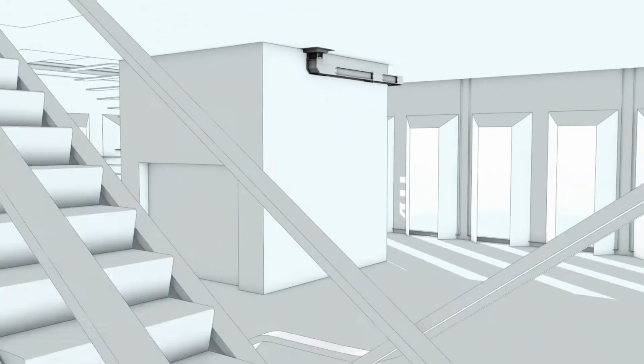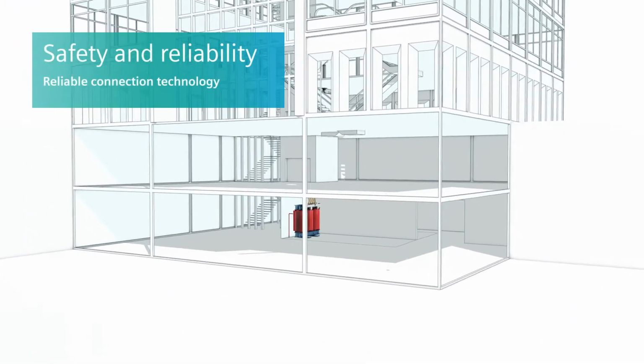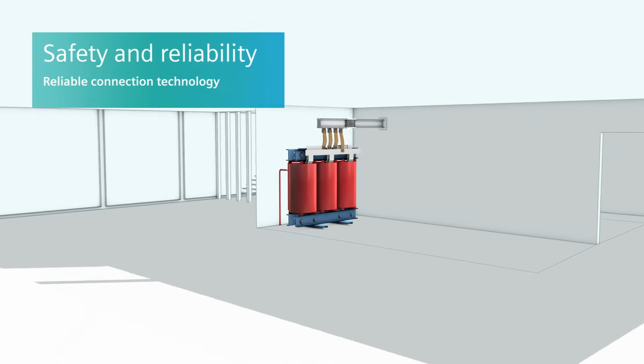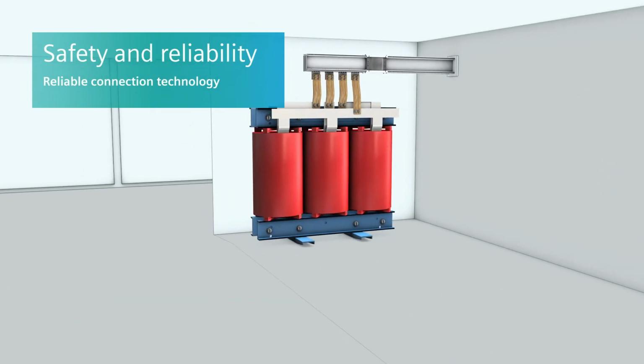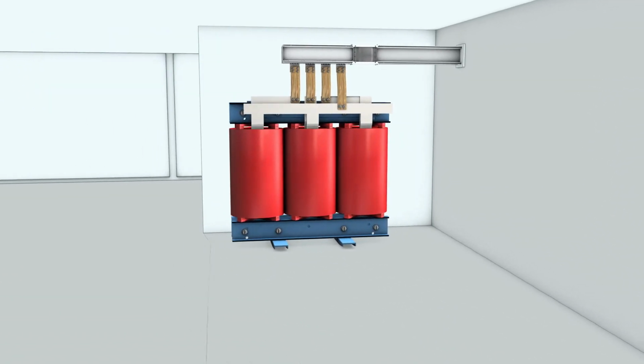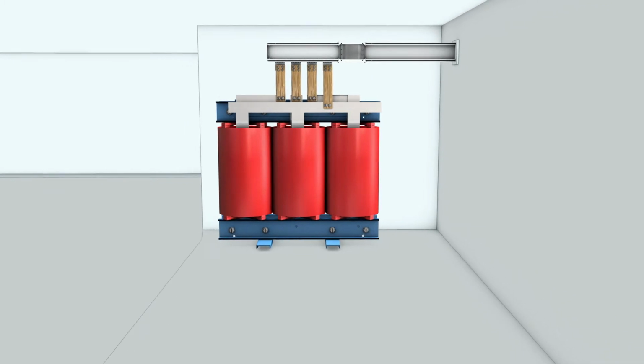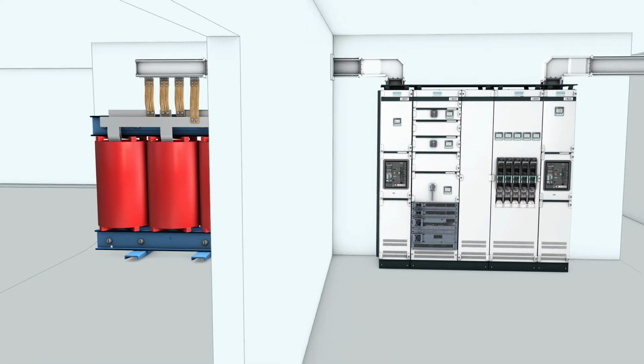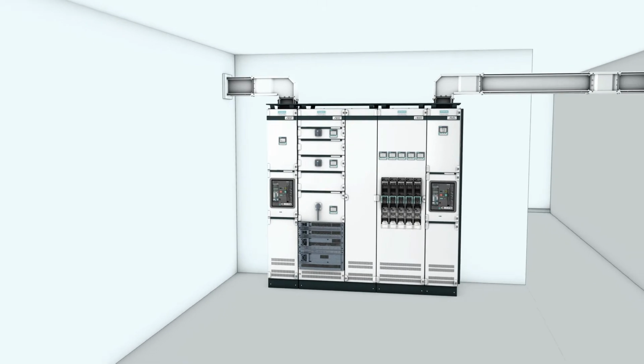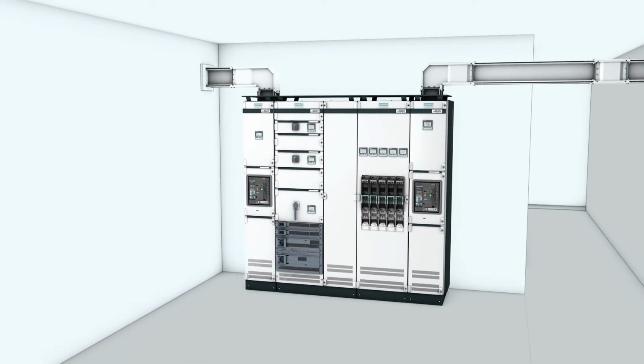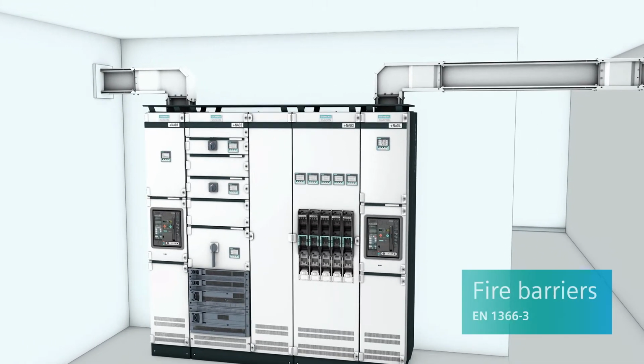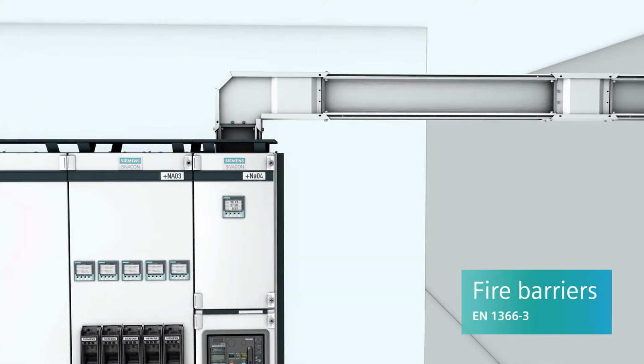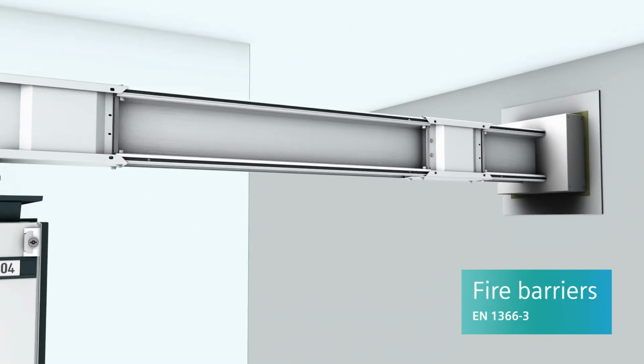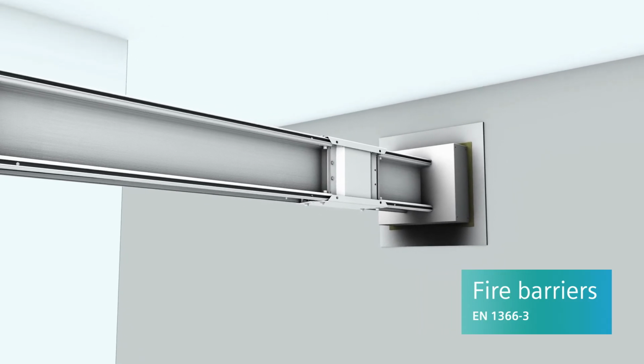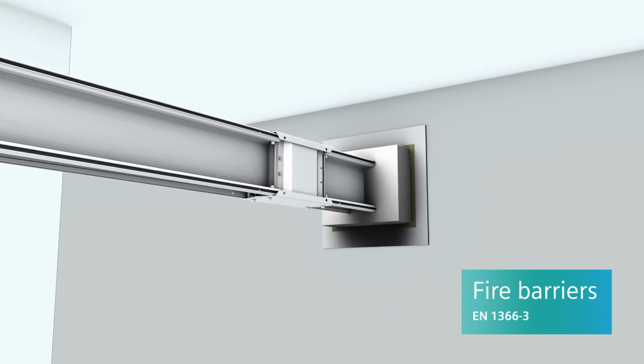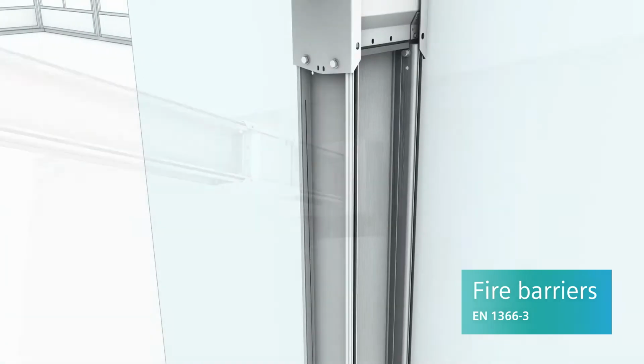When in operation, the LI system leverages its strengths, demonstrating safety and reliability in all applications. The connections for transformers and design-verified connection to the SIVACON S8 power distribution boards provide maximum plant safety. Does your installation require fire barriers? Then equip the busbars with EI90 or EI120 fire barriers at critical points, and you'll meet current building safety standards.